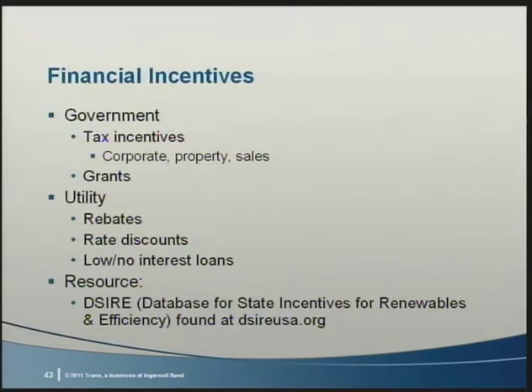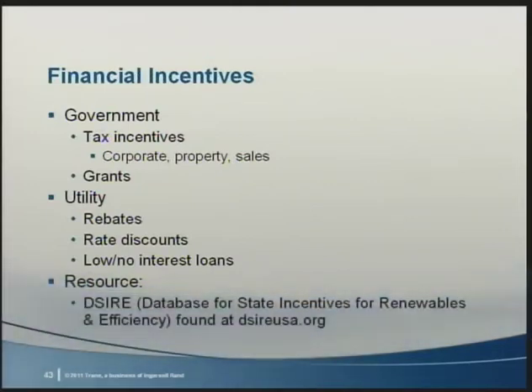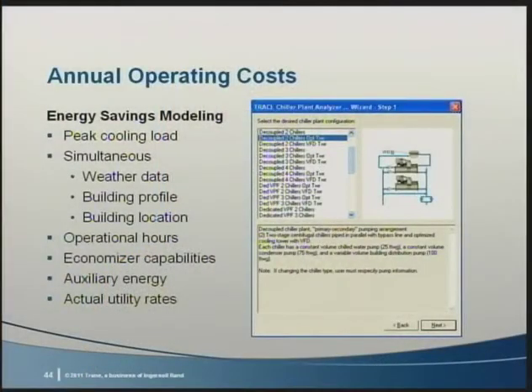Now there's a great resource at DSIRE, the database for state incentives for renewable and efficiency. This is a project of the North Carolina Solar Center and the Interstate Renewable Energy Council, and it's funded by the US DOE. So what type of analysis should be performed in determining the potential energy savings? I'm a firm believer that bin analysis is not valid since load and condenser water temperatures are not coupled. The tools should simultaneously account for actual load and weather, operating hours, number of chillers, economizer capabilities, pump and tower use, and the actual utility rate. There are tools available that allow such analysis to be performed in 30 to 45 minutes.